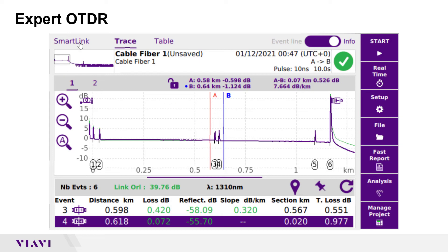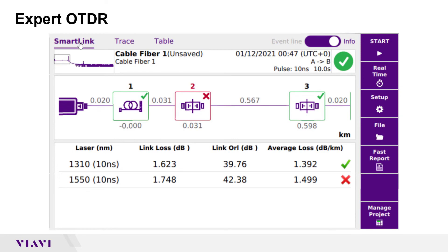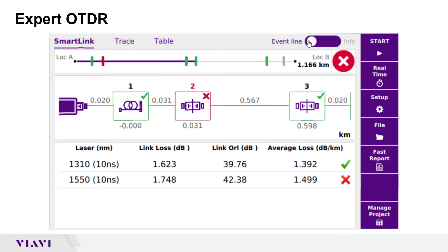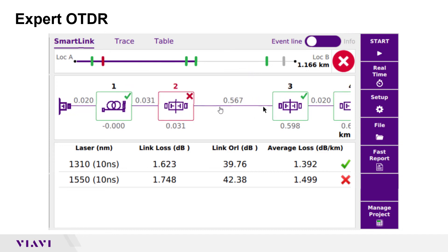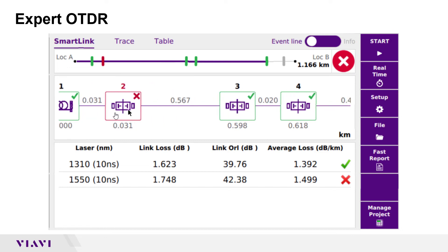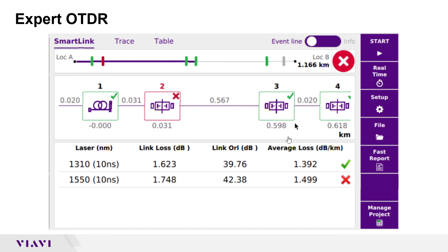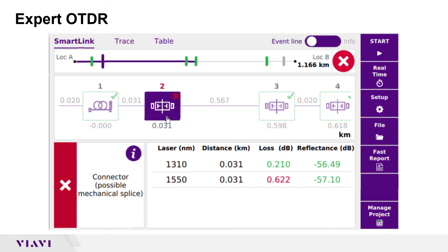SmartLink offers a simpler icon-based view of the fiber under test. When SmartLink is selected, I recommend the event line view, which shows all events on the fiber under test. If there are more than four events, swipe left and right on the main display to select the icons to view. In the center display, you can view summary results for each acquisition. Events are marked with a green check or red X based on pass-fail settings. You can tap on any event to view detailed results for that event.